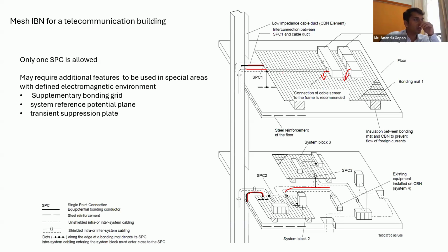So basically, when you are going to do an isolated bonding network, this system should have one single point connection to the earth. So your telecommunication bonding requirement must have one single point connection, and it should be isolated from the reinforcement. So it should not be connected. It should not be laid along with your reinforcement steel either.